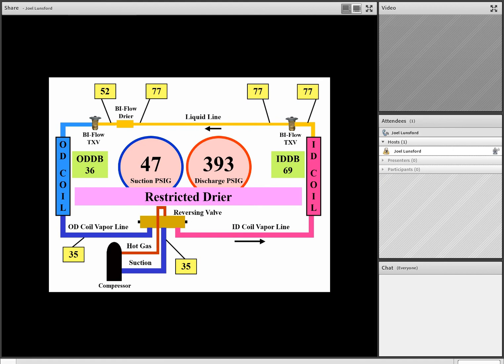In this example here, we have another 410A system. And as we take a look at it, we see it's in the heating mode of operation. Across the two coil lines of the reversing valve, we see that's about normal. We only have about a 1 degree difference. We see the BiFlow TXV on the indoor coil in the heating mode of operation should be flowing freely. And we've got about a 1 degree temperature difference across there. That's normal. But now, team, on this particular service call, you'll notice we have low suction pressure, and we also have a very large temperature drop across the liquid line in this case. So in this example here, we've picked up on this.